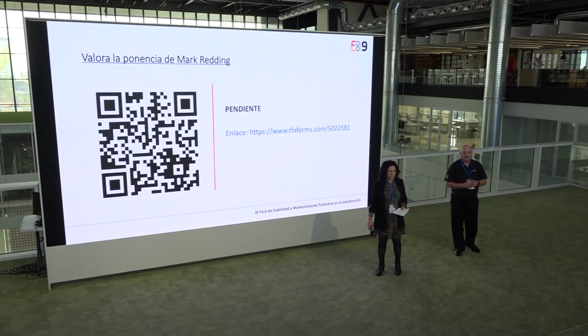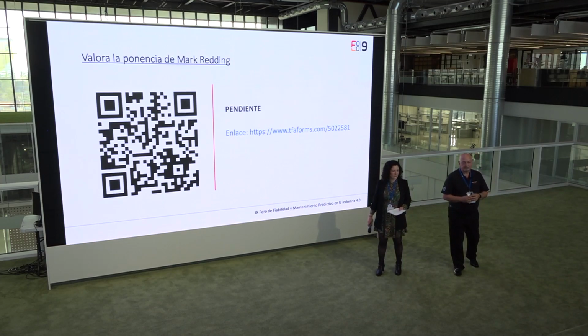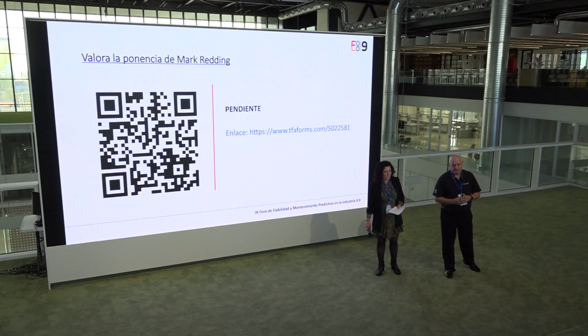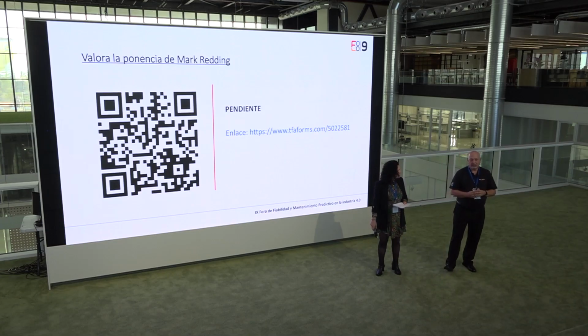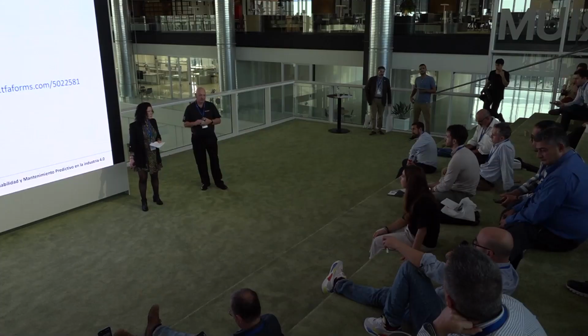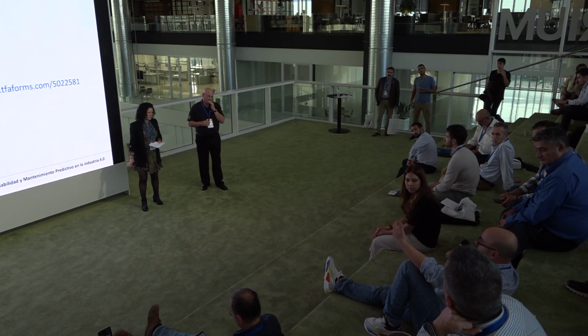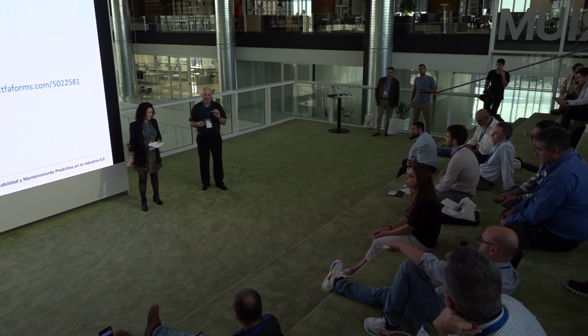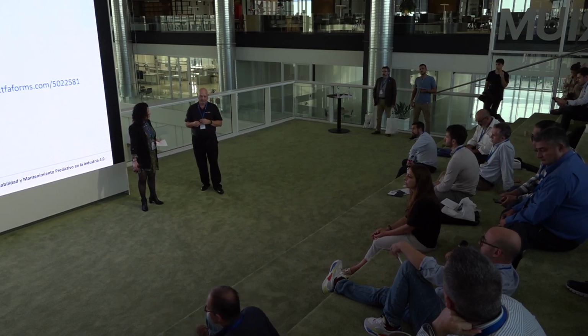Sorry. How many kinds of sensors do you have, and for which purpose? As I see, you can measure non-magnetic and magnetic particles, but how many types of sensors do you have? Are they dedicated only for machinery or mechanical parts, like rotating turbines, or also for electrical components like transformers? For example, if we want to measure DGA, can we measure it? No, we don't offer a DGA sensor, but the oil quality sensor can measure the properties in the transformer oil itself, as opposed to measuring the gases in the headspace. Okay, and can we differentiate elements like nitrogen, oxygen? No, but it's sensitive to the degradation of the transformer oil. Okay.